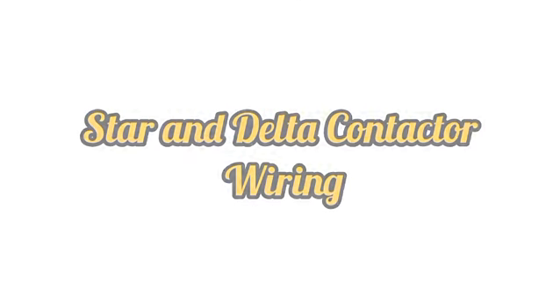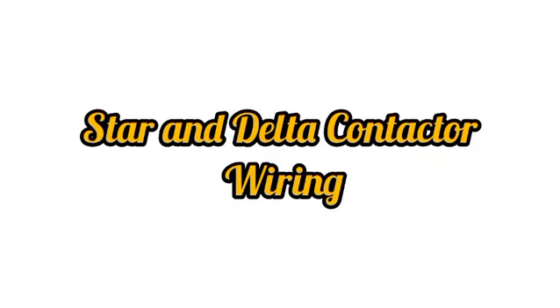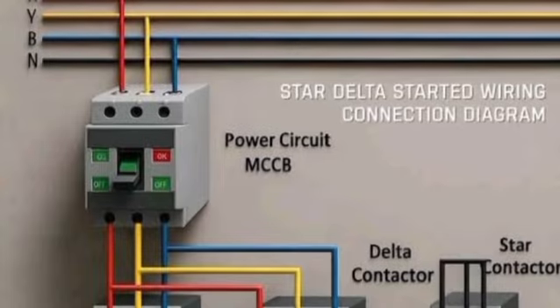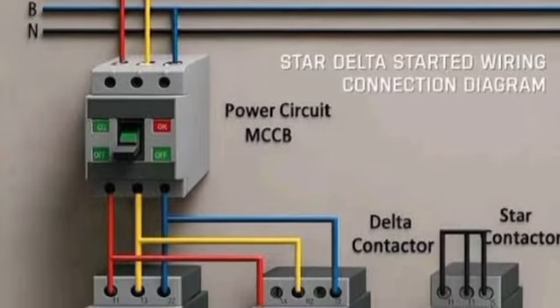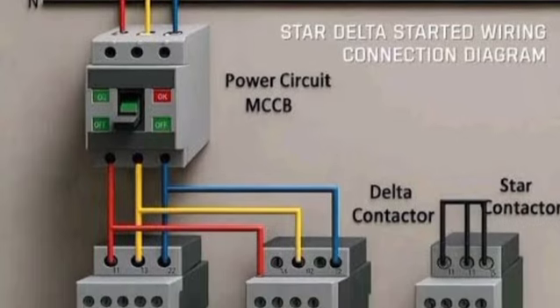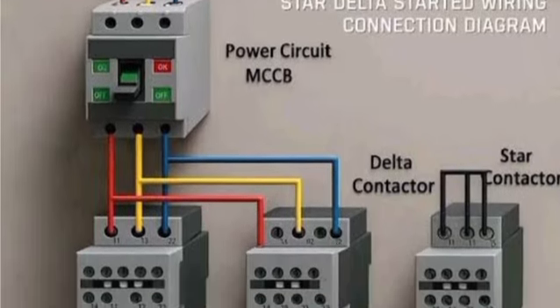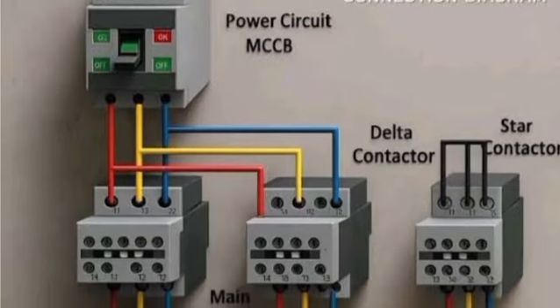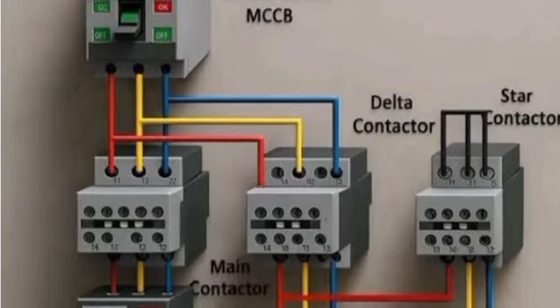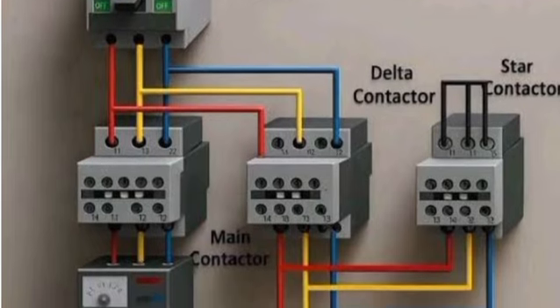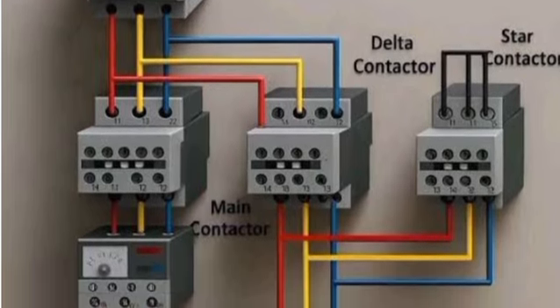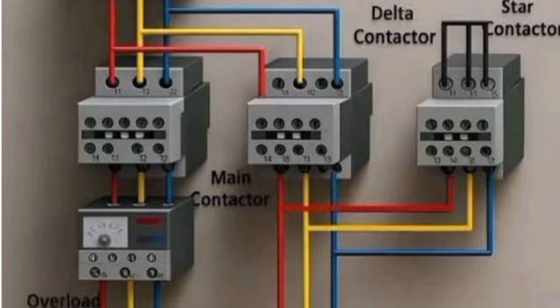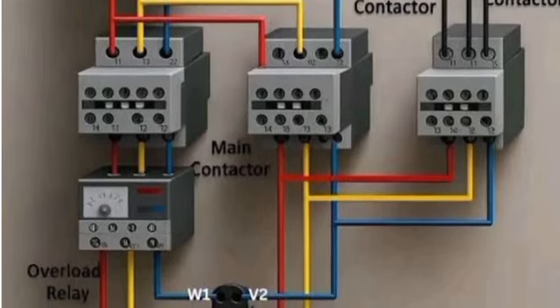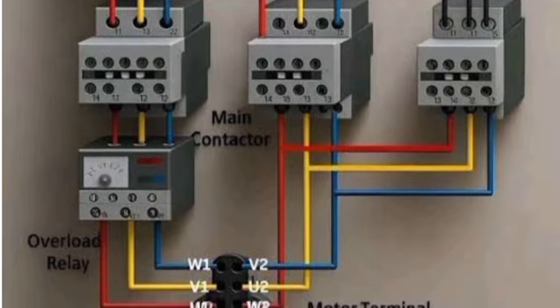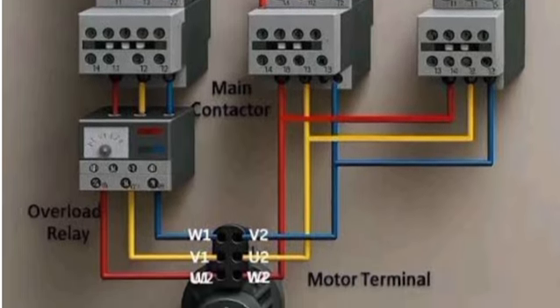Star and delta contactor wiring. Wire the star and delta contactors according to motor terminal configuration. Ensure interlocking between contactors to prevent simultaneous operation. Correct wiring prevents short circuits. This stage is crucial when understanding how to connect star delta starter safely. Interlocking improves safety and ensures smooth switching between star and delta modes.